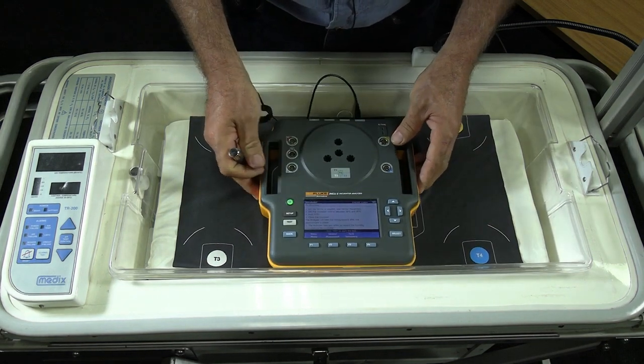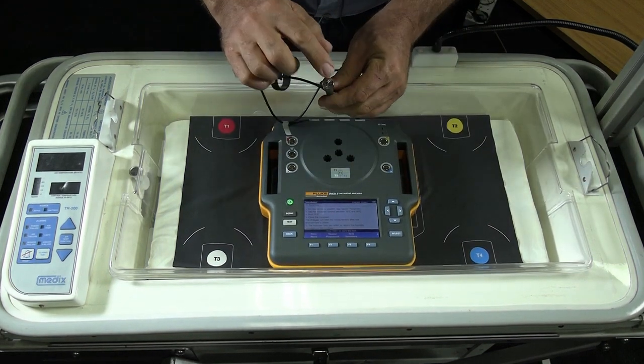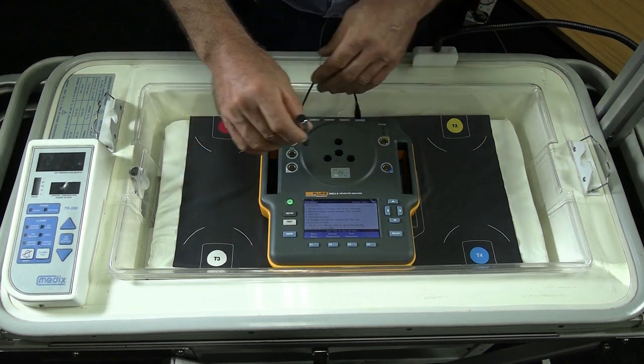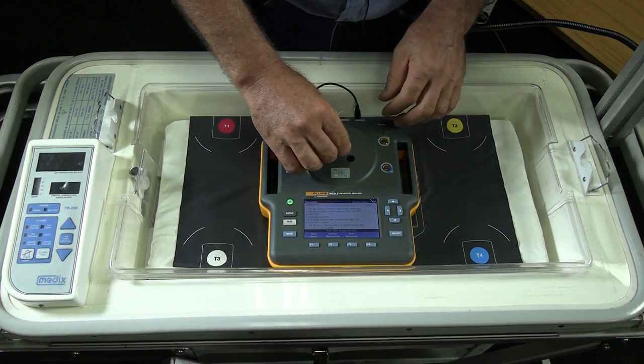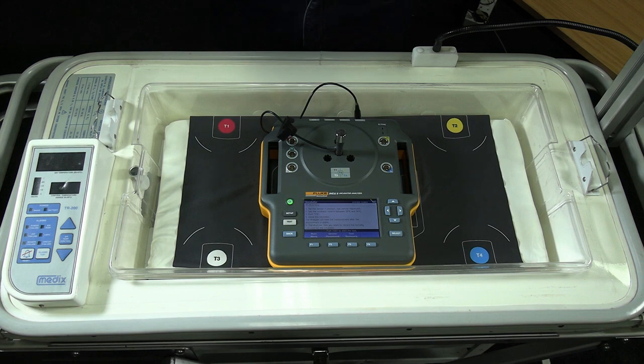put our sensor in place. You'll notice this looks like a little microphone. That's what it is. Place it into the sensor. The two tests you'll be doing on the inside of the unit will be measuring the alarm levels, sound levels inside the unit, and also the environmental sound inside the unit coming from your fans.